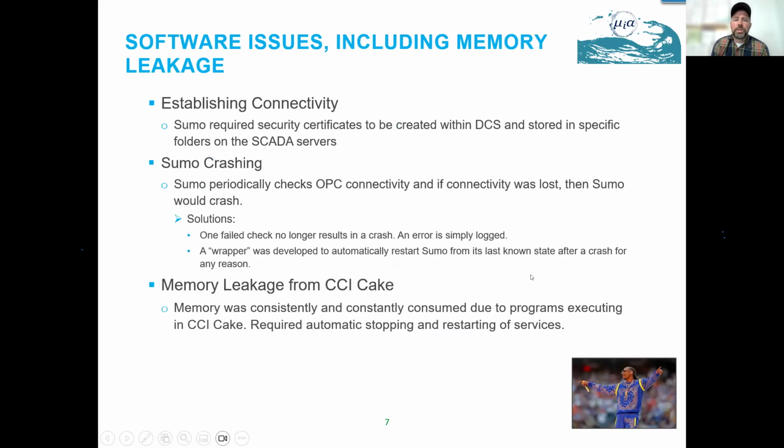So a number of other challenges here. Some of them include, it took us almost a year to establish connectivity between the distributed control system and Sumo, and that was due to some security certificate issues that we had to work through.